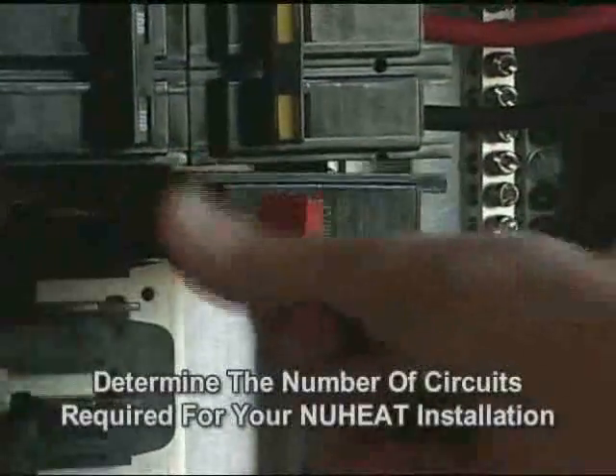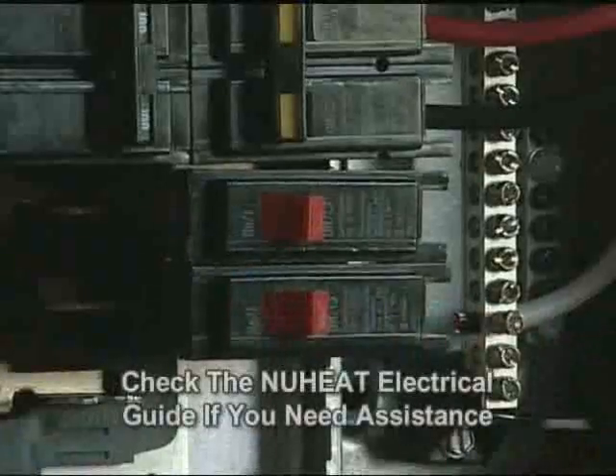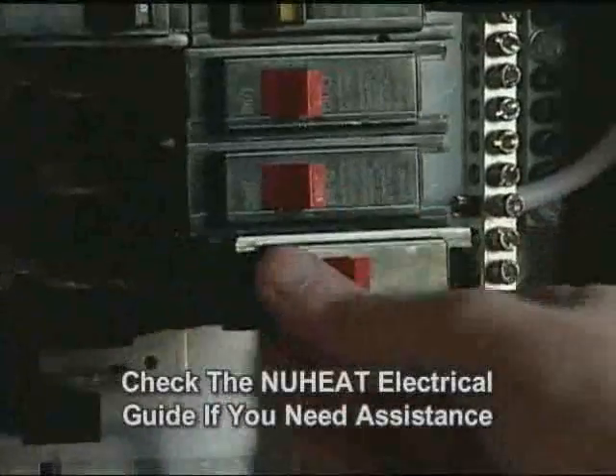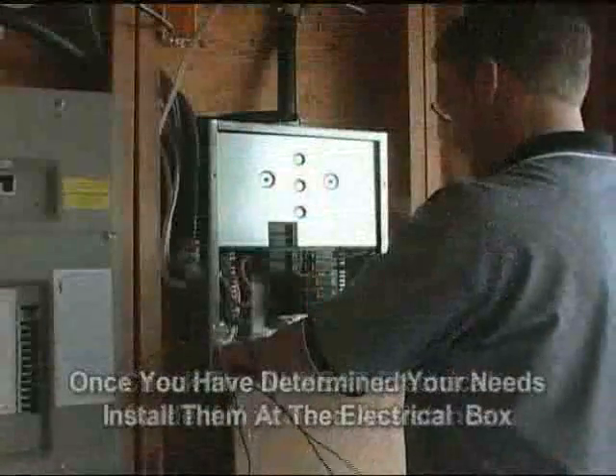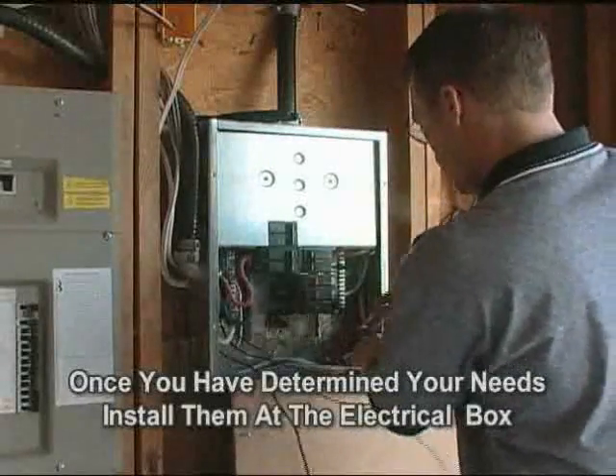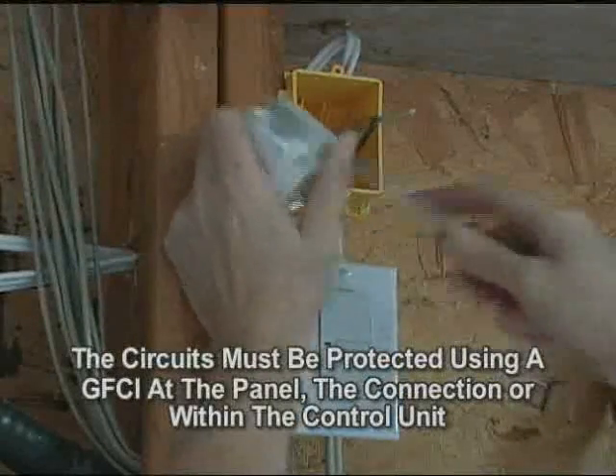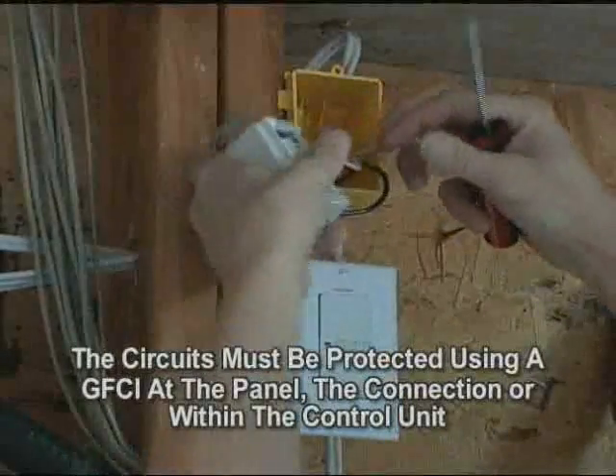Begin by determining the number of circuits you require for your NuHeat installation. Check the electrical guide if you require assistance. Once you have determined the correct number of circuits, install them at your electrical box. Remember, these circuits must be protected by a Class A GFCI, either at the panel, at the connection, or within the control unit.